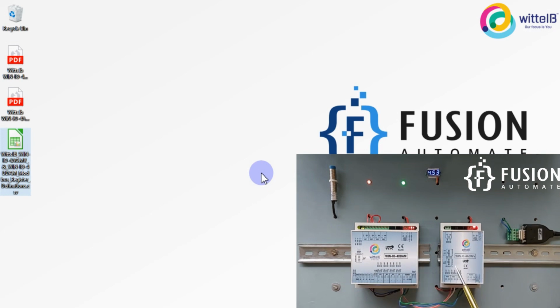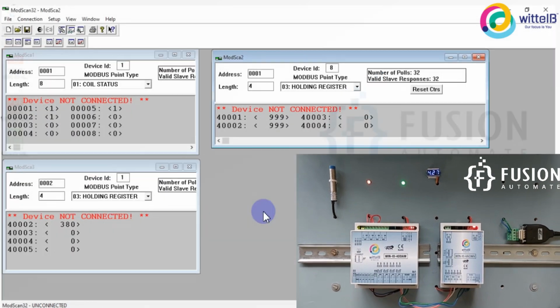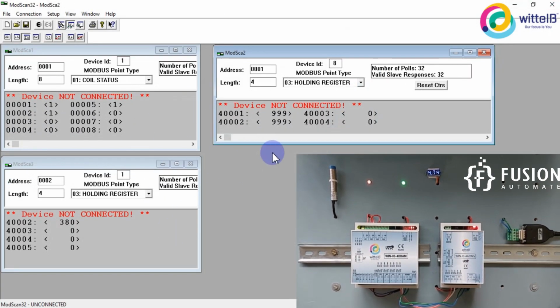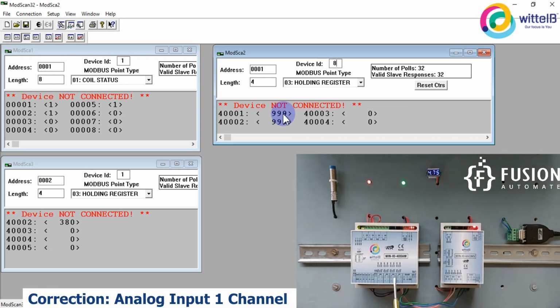Now we will open the Modscan software and try to understand the register settings of these two Modbus IO cards. Here I have my Modscan open, as you can see on the screen. This window is specifically for the digital output and digital input channels. The second window is specifically for the analog input channels, and the third window, with device ID 8, is specifically for the analog output channels. If we change any holding register value here, it will affect my DC voltmeter and also the analog input 1 channel of this card.